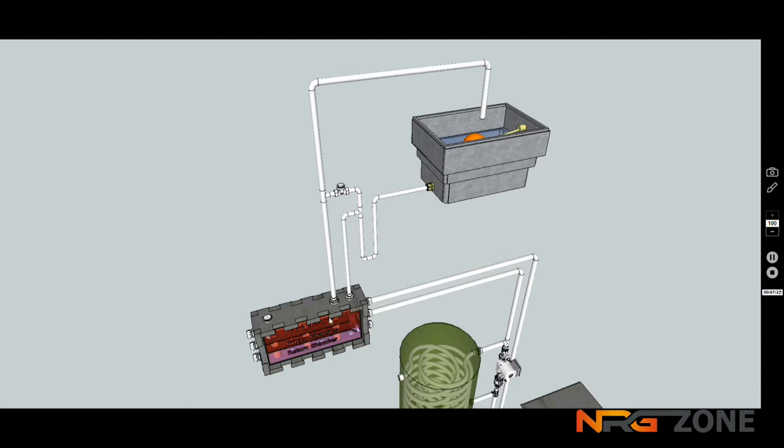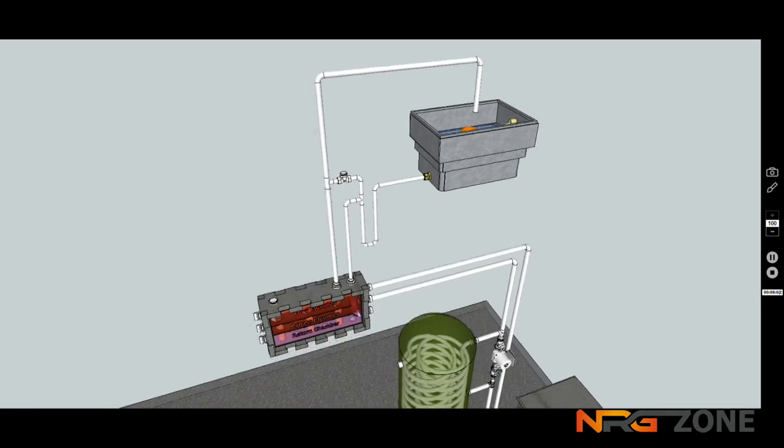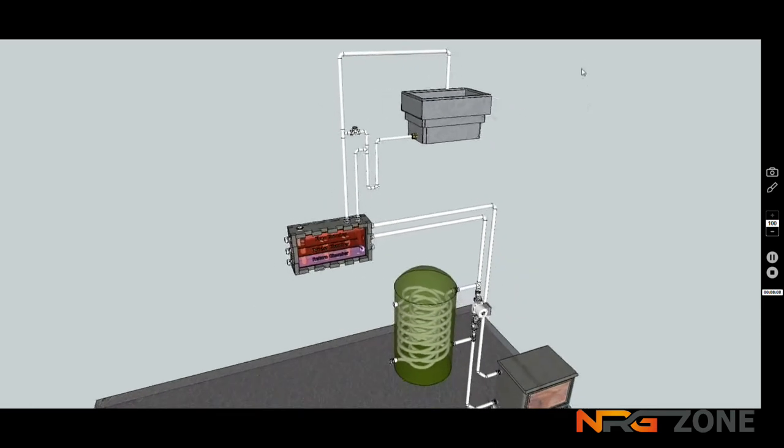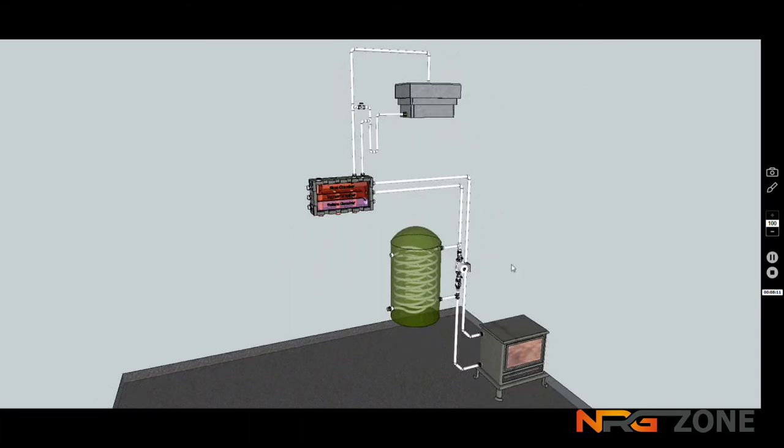In the meantime, where the air is rising up through here, and if there's any chance that some water might be pitched over into the tank, as water might travel up with it in the process of trying to spill over into the tank, at the higher any water goes in this pipe, it'll put pressure on this non-return valve. If that non-return valve has pressure, the gate will flap open, the water will flow through and back down again into the cold feed, so you'll get no pitching in this situation. This is particularly useful if you haven't enough room to get much height on the expansion above the heating tank, if there's some height restriction in the project that you're doing.